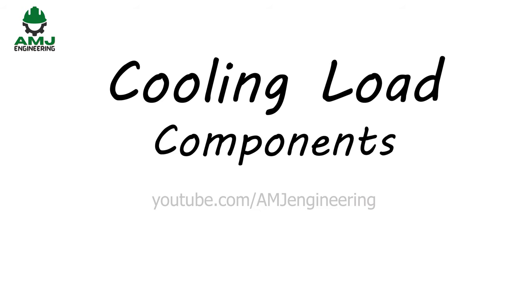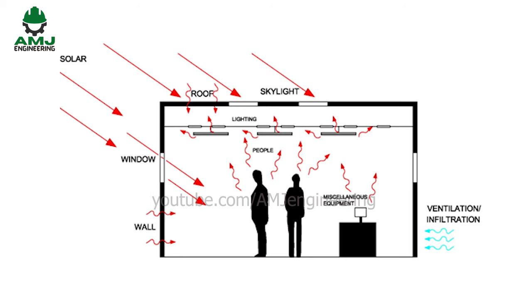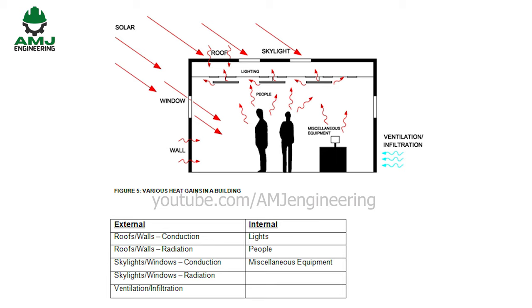First, let us indicate the various components that constitute the cooling load on a building. We have two types of heat gains: external and internal. External heat gains result from heat transfer by conduction through walls, roof, floor, and doors, and by radiation through fenestration such as windows and skylights — all sensible. Additionally, heat gain due to ventilation and infiltration includes both sensible and latent components. Internal heat gains come from occupants, products, processes, appliances, lighting, and other equipment.